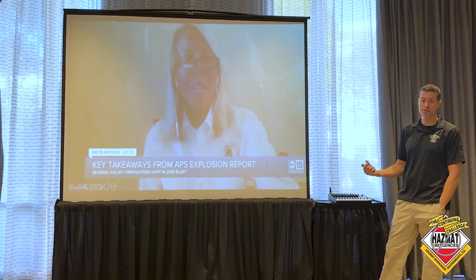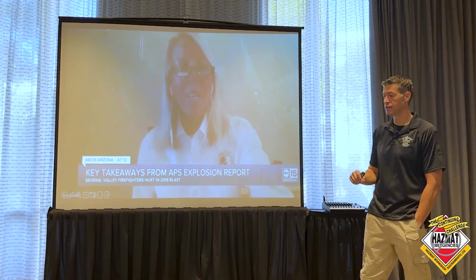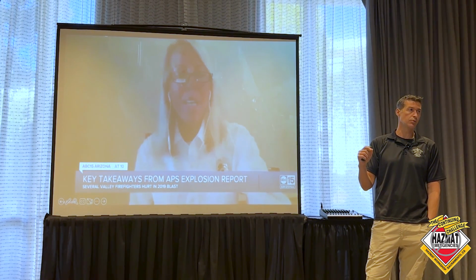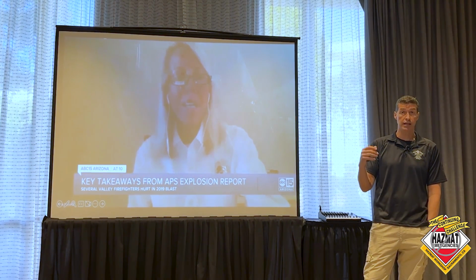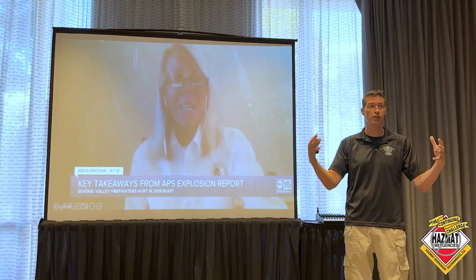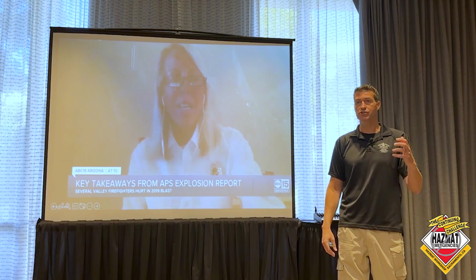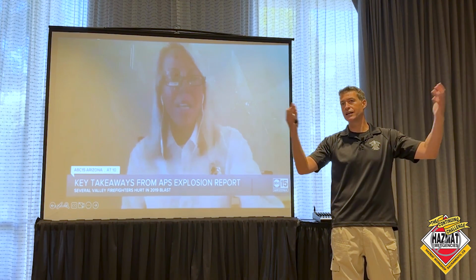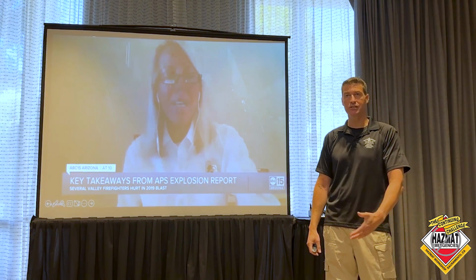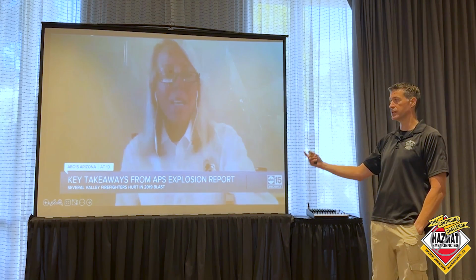One of the things that's interesting about this, and I'm not an expert on this system, there are definitely experts out there that have been involved in the study of this, but they identified that the inert extinguishing system that was in place worked great. It went in, and the batteries are not just the batteries, you get the plastics on the outside of the battery, the little box and all, so that stuff was on fire. The inert system went in and put the fire out. When it put the fire out, the fire was mitigating some of the hydrogen gas that was present. So they put the fire out, now you let hydrogen gas build up. So they identified that actually the inert extinguishing system led to a buildup in hydrogen inside that container, which then led to the explosion, which then injured all those guys.